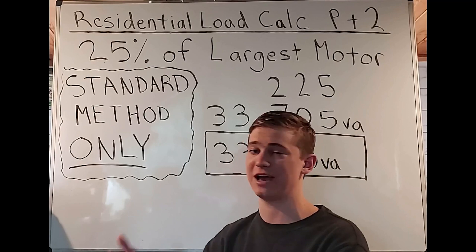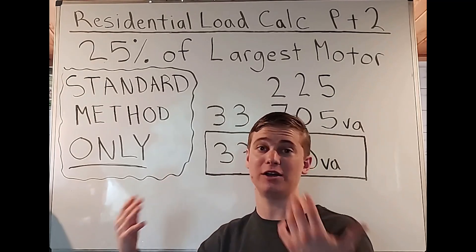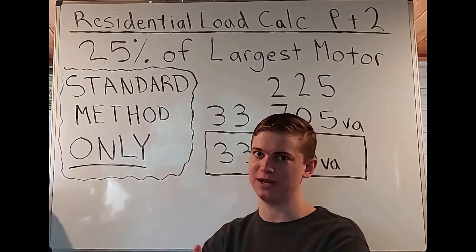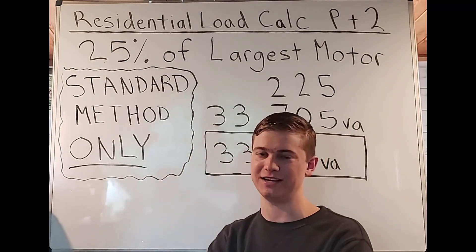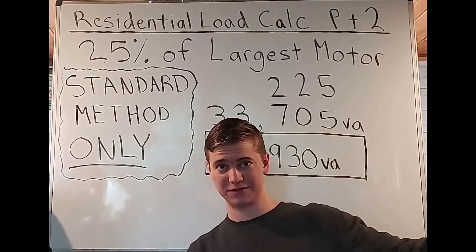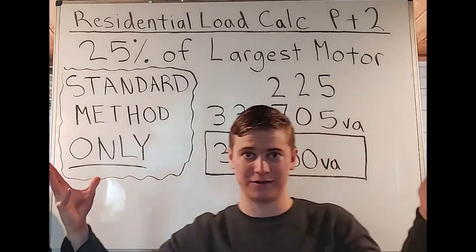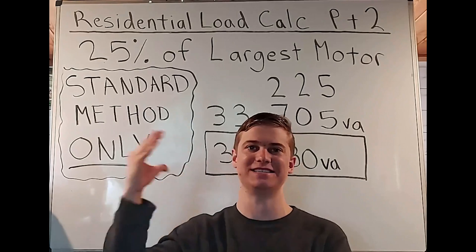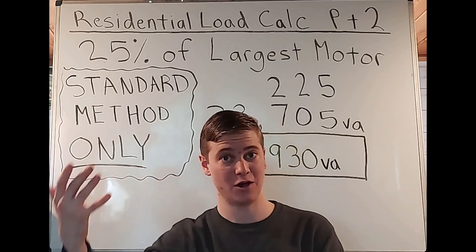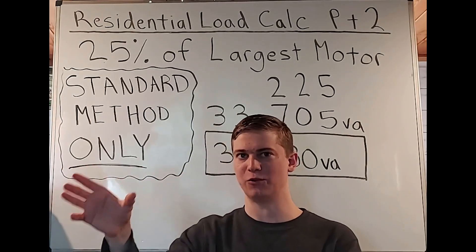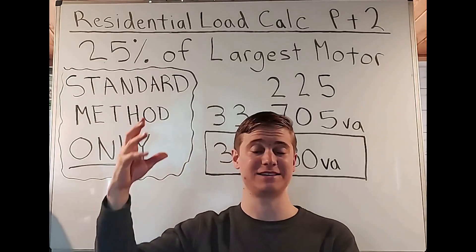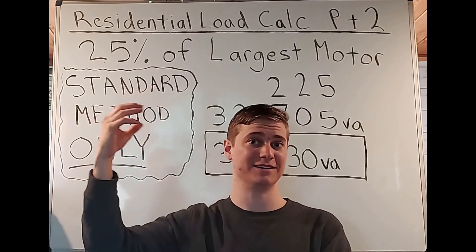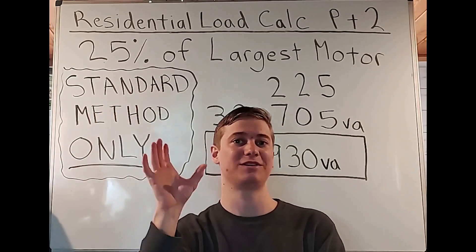All you're going to do is look at your appliances, not including your dryer and your range, of course, because those are separated in the calculations explained in that last video. But other than that, the other fixed appliances in the house are the appliances with a dedicated circuit home run. We're going to look at those and we're going to take the one that has the largest motor.